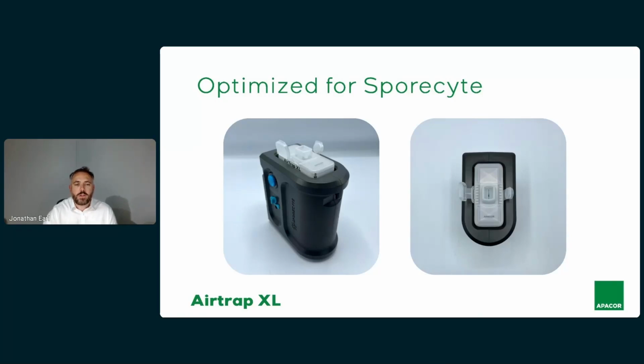And hopefully you can imagine with this hinged cap approach, as you go to place the cassette onto your pump, you open the bottom inlet as you put it on. Like I say, it's almost a one-handed operation, and you don't need to open the top inlet cap until you're literally about to press go on your sample collection. And then conversely, at the end of your sample collection, you just close the top cap before you've even taken the cassette off the pump. And as you pull the cassette off the pump, you just close the bottom cap.